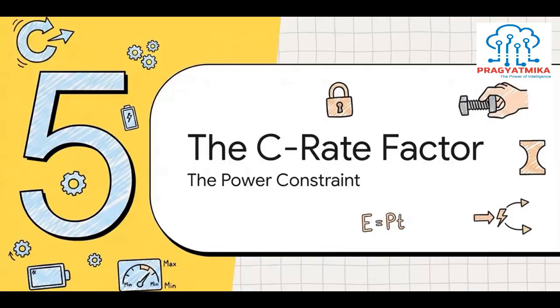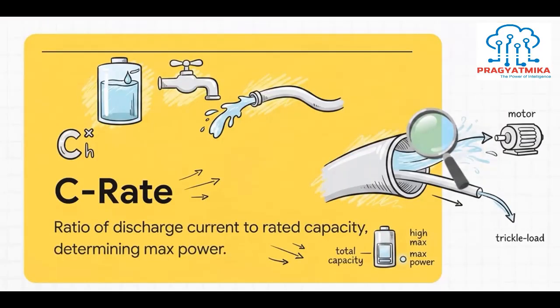The C-rate factor, the power constraint. Finally, we have to bring this entire calculation back to our primary power bottleneck. C-rate measures how fast a battery discharges relative to its total capacity. This means a battery might actually have all the required energy in kilowatt hours, but completely lack the discharge speed to start a heavy load. It's like plumbing. It doesn't just matter how much water is in the tank, it matters how wide the hose is to let that water out.